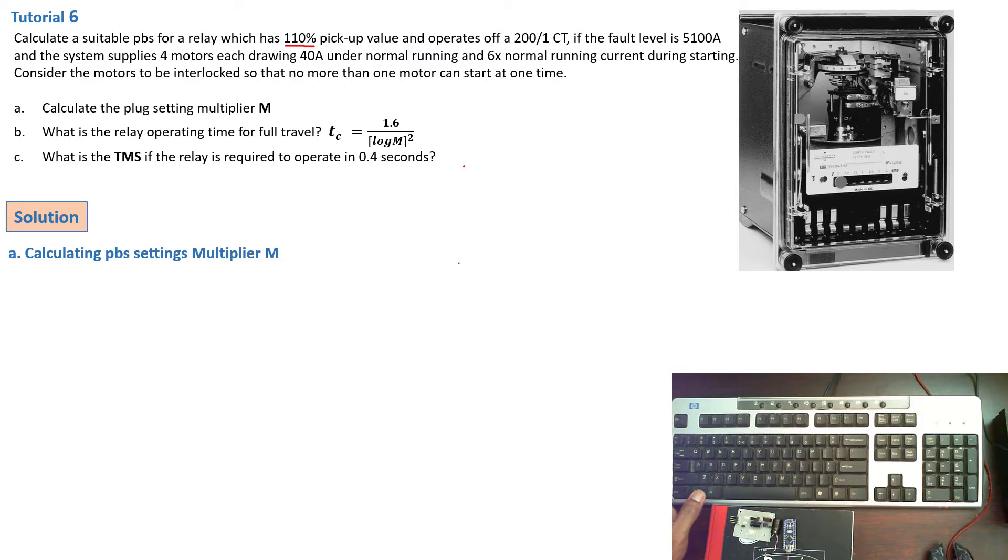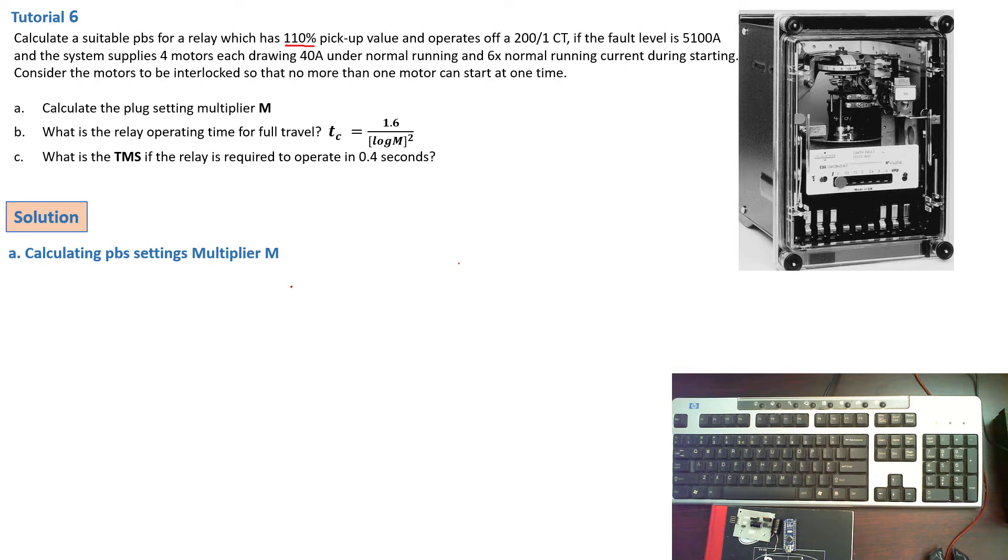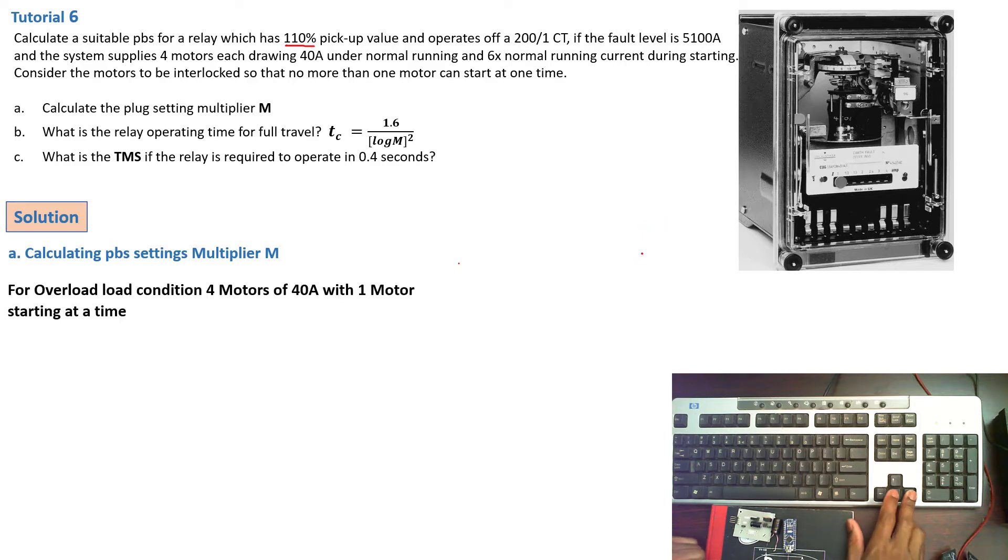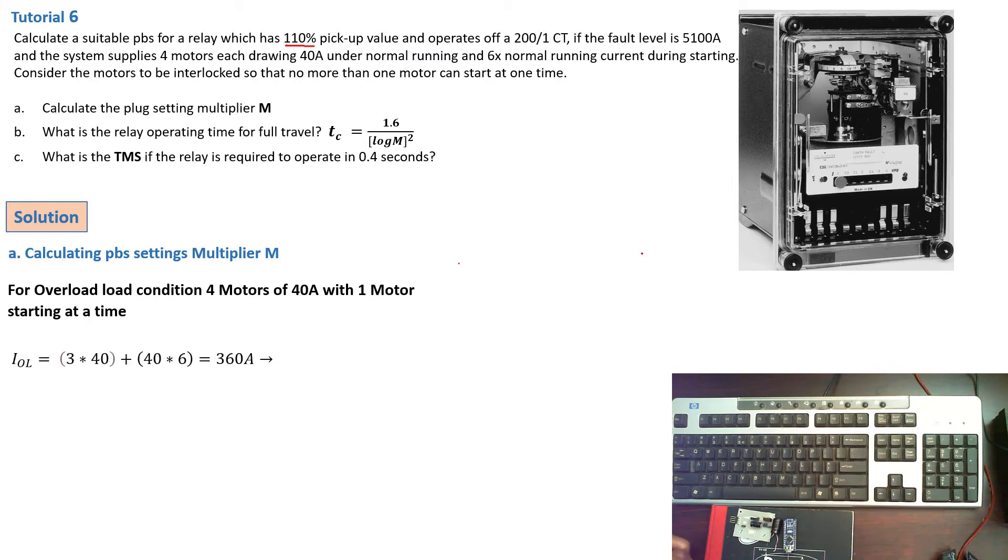We must understand now here that to calculate for overload condition, we must consider the condition where there is the highest overload current. So for four motors, that means they are interlocked. So one is starting at a time. So the highest overload condition will be when three motors are running and then the fourth one is starting.